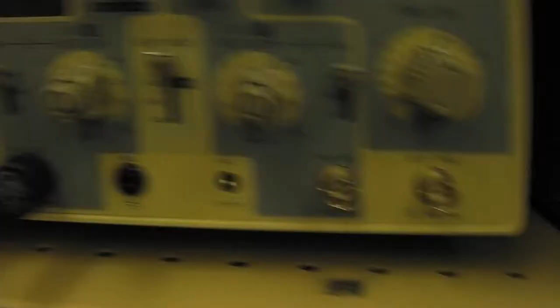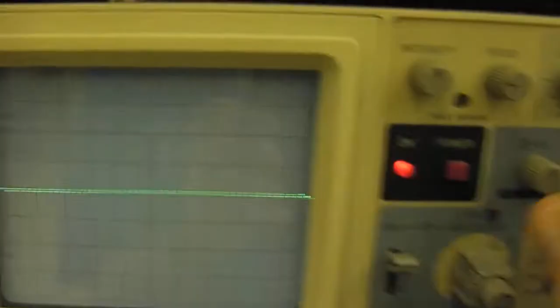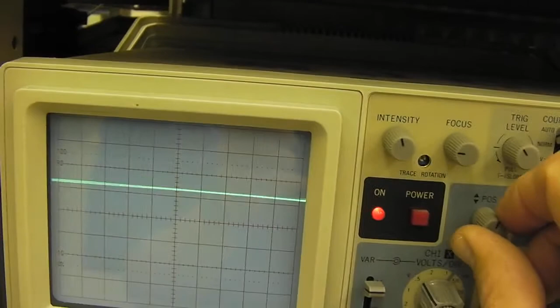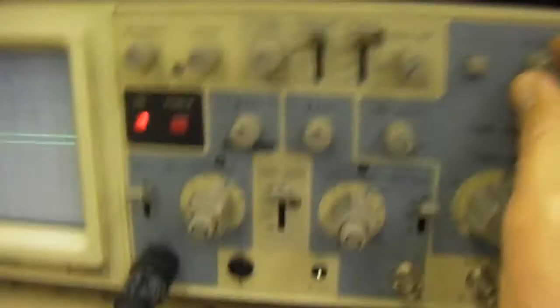Okay, and then the next thing it tells us is, it says a trace line should appear, and we can move it to the center of the screen using the vertical and horizontal position control knobs. Well, I was using the vertical knob here. That moves it up and down. And there's also a horizontal control knob over here, and that moves it sideways. In other words, if the line isn't centered on the screen, you can move it sideways with that.